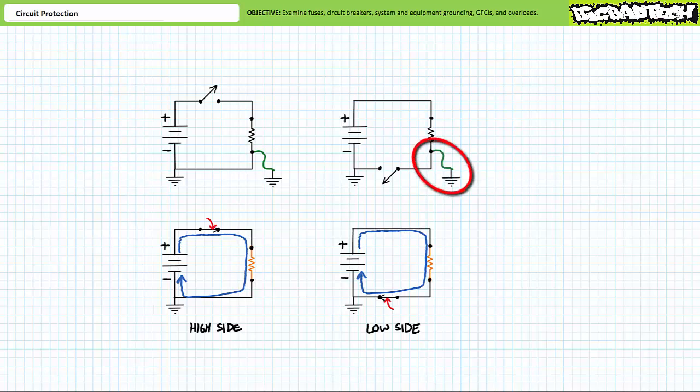Not so in the low side switched arrangement. The electrical load is always connected to the source and only necessitates a connection to ground to run. Any errant connection to ground can energize the electrical load even if the low side switch is open. Be extremely careful when working around low side switched elements.